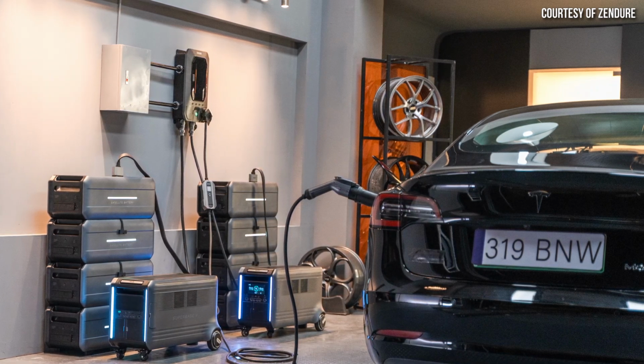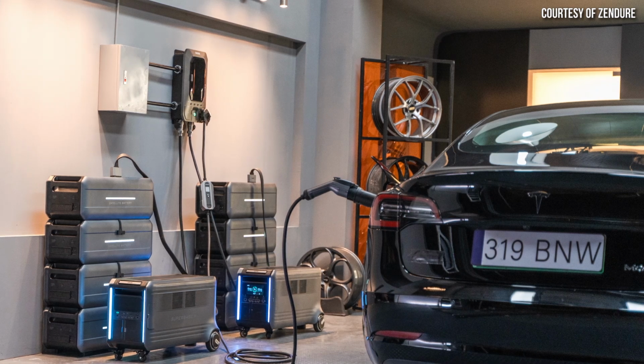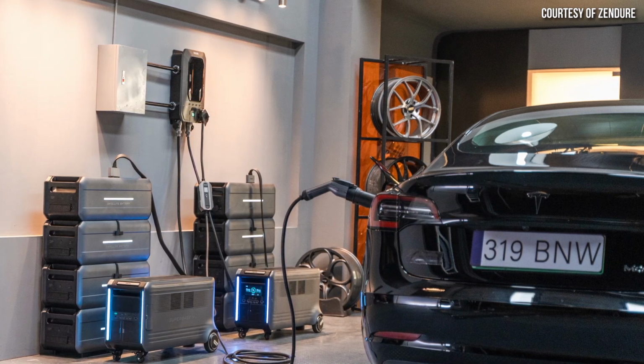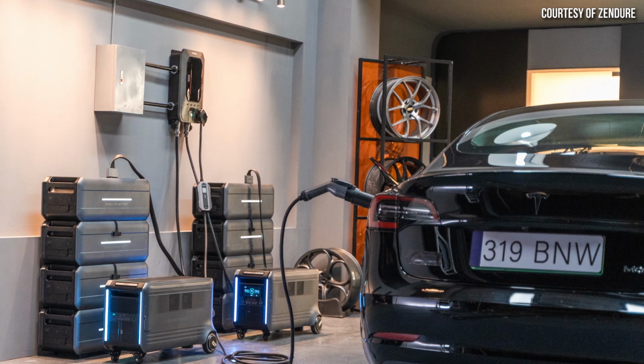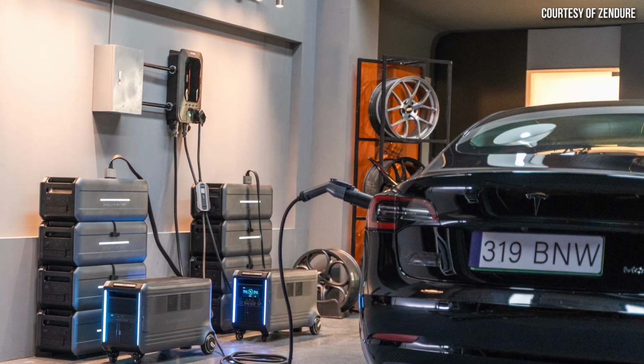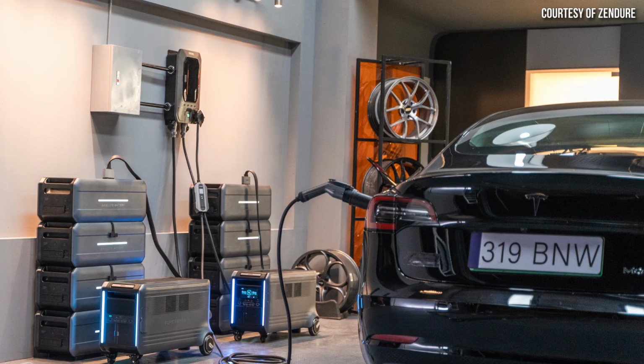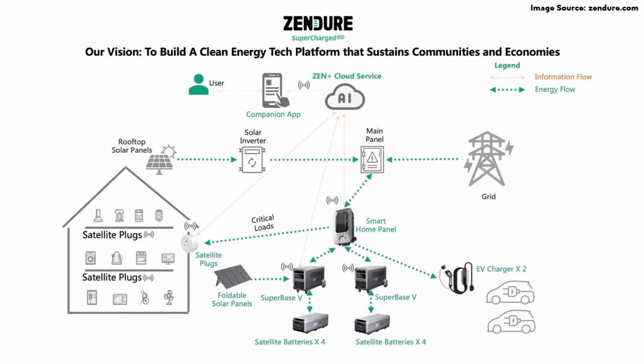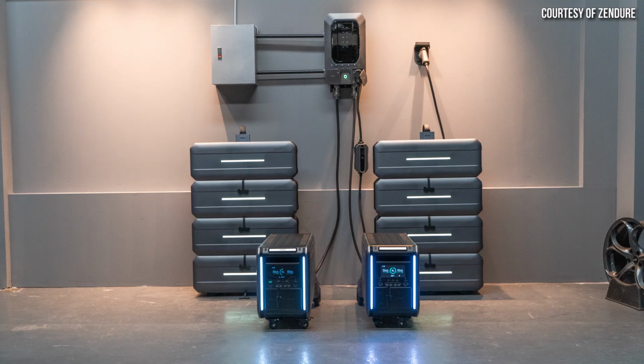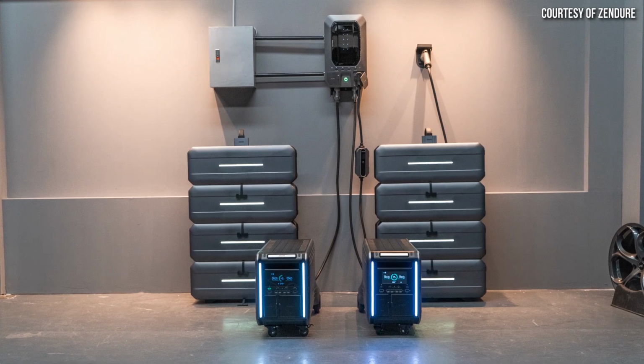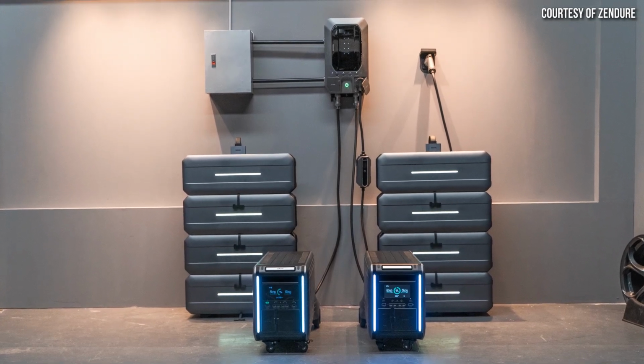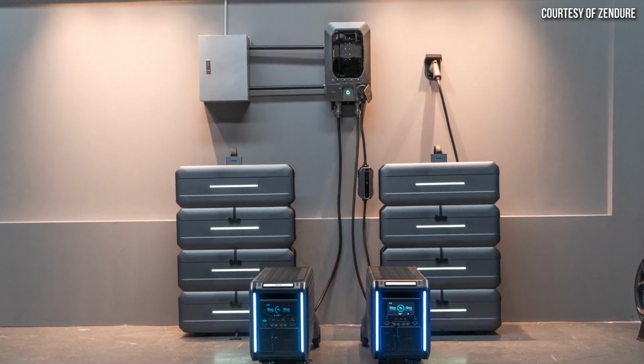This Zendure Smart Home Panel will act as a smart load side transfer switch, with the option to connect up to 10 critical load circuits, which can be powered by your Zendure battery backup system in the event of a power outage. Zendure told me the home panel will automatically switch connected circuits from grid power to battery backup power during an outage with a response time of 20 milliseconds. If you opt for that home panel in the future, it also has 2 outlets on the side that allow you to connect EV chargers directly.